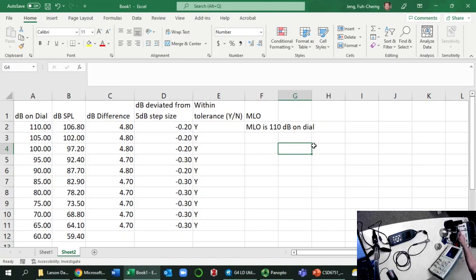Let me change it to, say, 125 hertz, and then let me try to go up. It can only go up to 70. It cannot go up any further. How come 1000 is 110 and 125 hertz is 70? Because they set it within the audiometer. And how come they set it? It's because they calibrated the linearity. They only let you use it when it's within linearity tolerance. Otherwise, it won't be very accurate. If they allowed you to use higher intensity that goes beyond the tolerance, the result would be inaccurate.